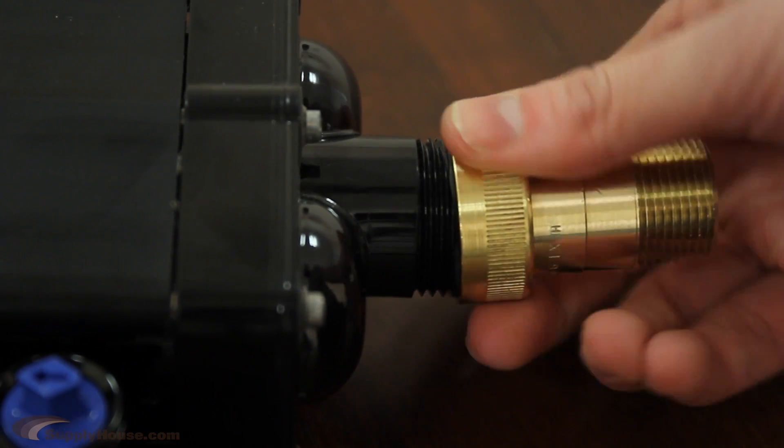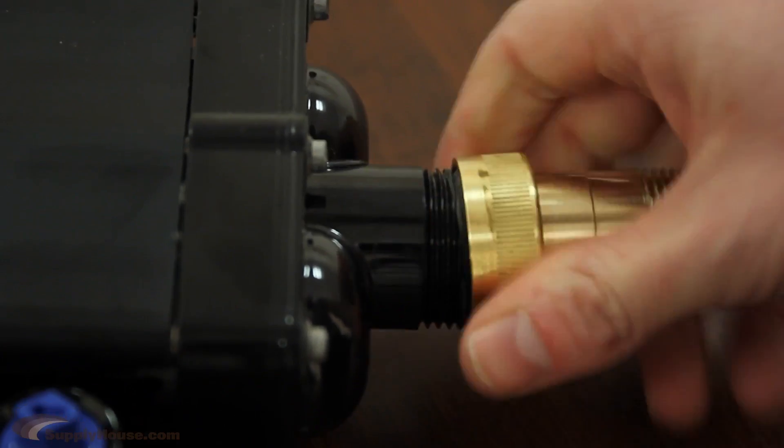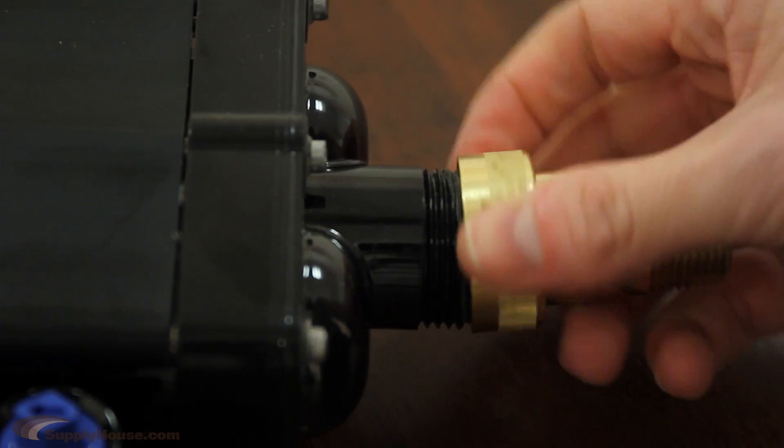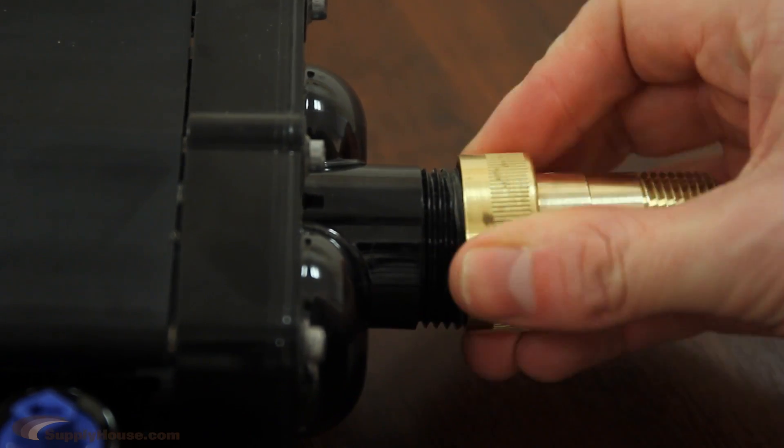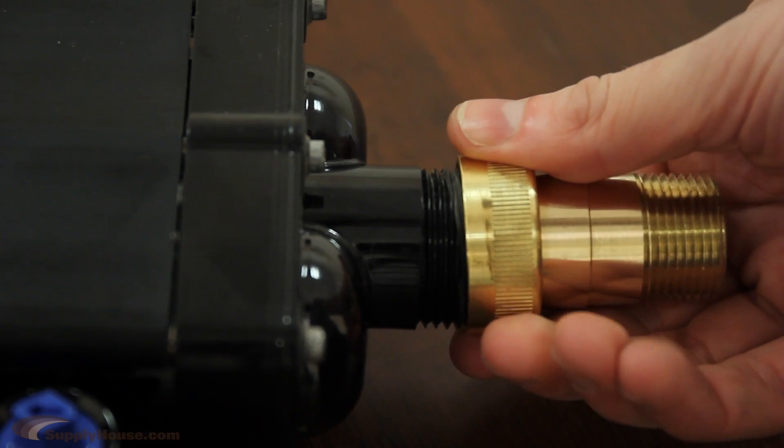The metal threads on the supply adapter are tougher than the plastic threads on the mana block. So if you get it going and force it and it's not going easily, you're going to strip the threads on the mana block.